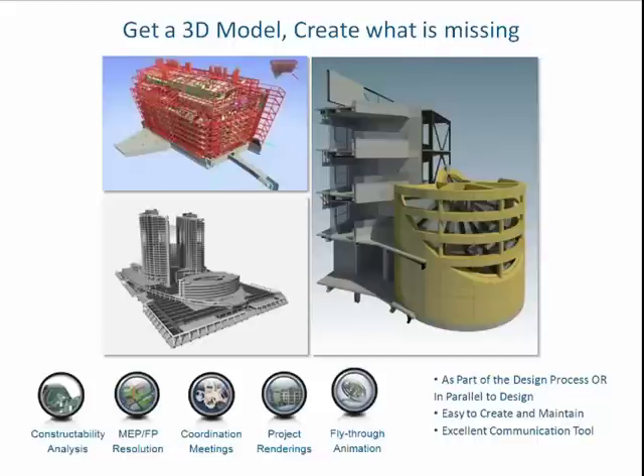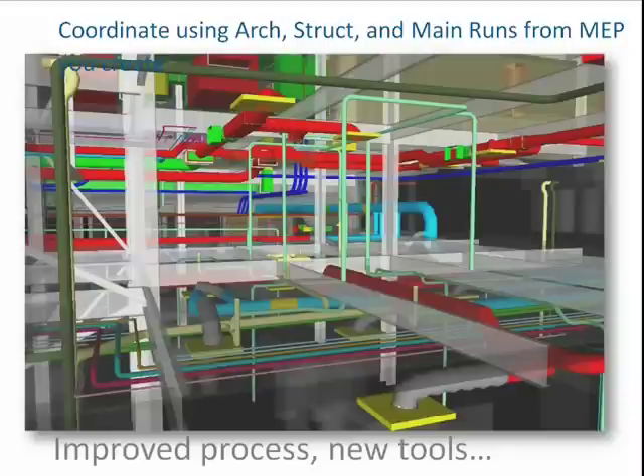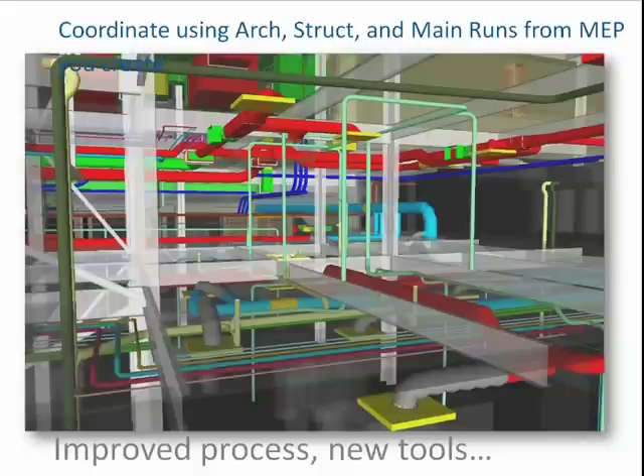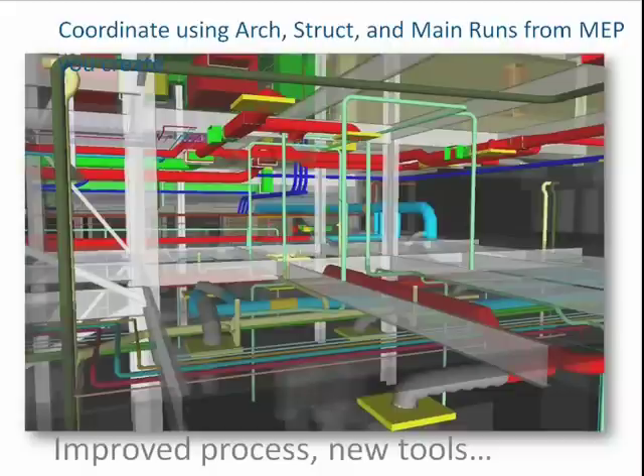Getting the main runs coordinated early is really important — not just against the systems themselves, not just MEP, not just mechanical against electrical, against plumbing, against fire protection, but getting those slab penetrations and any of those structural issues, beam penetrations, out of the way early is really important. Very, very helpful to the project and overall time.